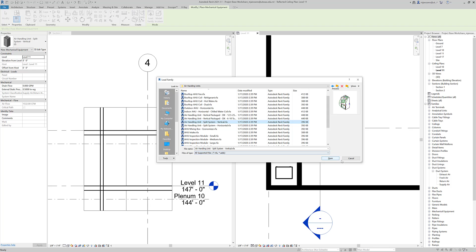We're going to go to Systems, Mechanical Equipment, and Load Family. We're still in the Air Handling Unit folder, but we need to use one of these Air Handling Unit Split System Vertical. This will let us load in a series of small vertical AHUs with a different orientation, so we can fit them in these mechanical closets we've designated as 5 by 5 foot rooms. We can probably use a 3 or a 5. Either one is probably okay. If you're really pushed for space, I'd use a 3, but the 5 is still probably undersized.